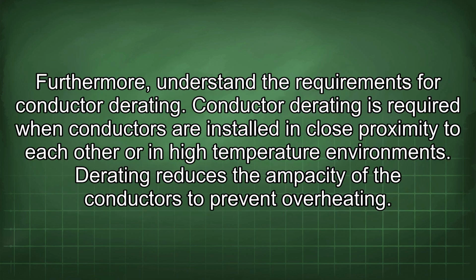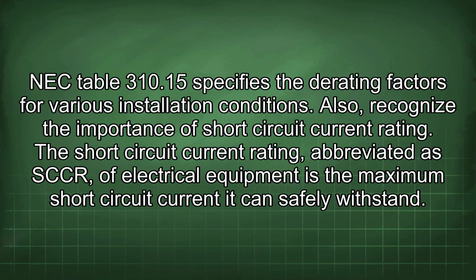Furthermore, understand the requirements for conductor derating. Conductor derating is required when conductors are installed in close proximity to each other or in high-temperature environments. Derating reduces the ampacity of the conductors to prevent overheating. NEC Table 310.15 specifies the derating factors for various installation conditions.